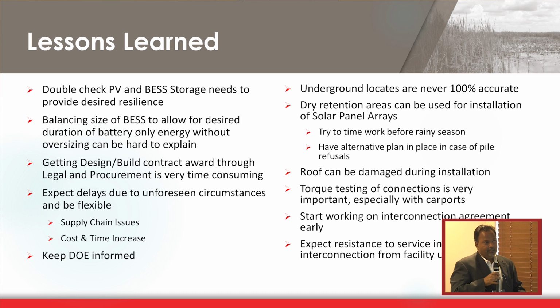That allows, in an extended outage, routine maintenance on the generators. So if it's running in an extended outage like a Hurricane Irma event, the BESS would run the facility for at least 3 hours. When the generator kicks in, it will charge the BESS while running the facility at the same time. After the battery reaches back up to 80%, the generator cuts off, and the BESS takes over running the facility for another 3 hours. That's how it's designed to work.